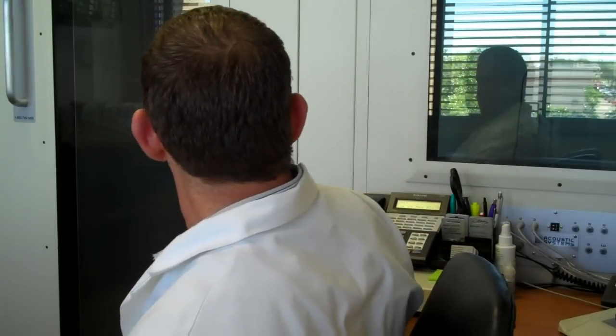Typically, with a custom-style device, since the sound intake on the device is located in your ear, we're going to recommend that you hold the phone directly over the device. Now, in some cases, you may have feedback in doing so, in which case we'd recommend that you simply tilt the phone a little bit off the ear like so. So instead of holding it flat against the ear, tilt it off the ear a little bit like so, and that's usually all that's necessary to rid of the feedback problems.